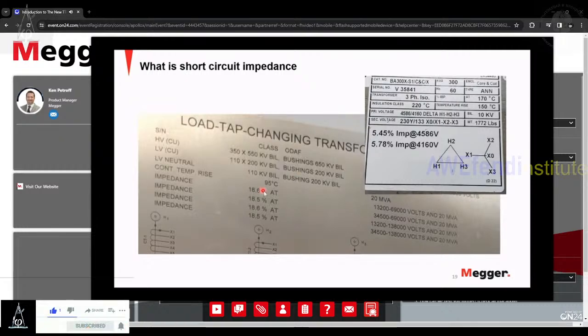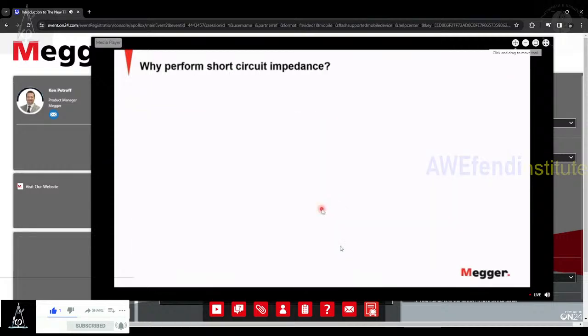This is another example on a different transformer where there's a percent impedance for each of those, specified at 20 MVA. And here the temperature rise is 95 degrees C. So this is what you have to look for on these types of transformers when you're evaluating the short circuit impedance value.